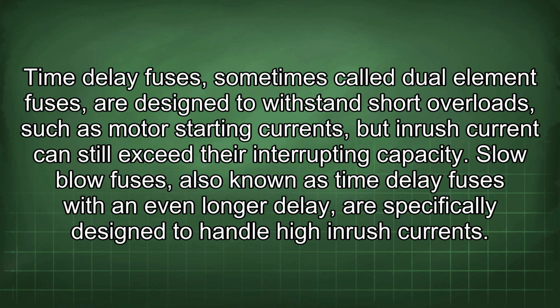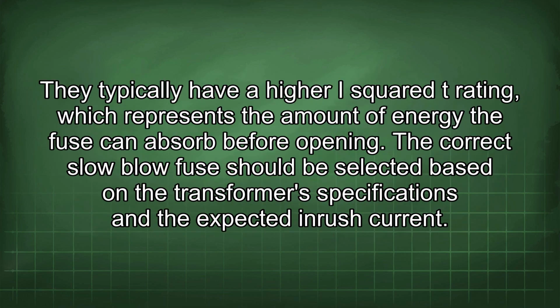Time delay fuses, sometimes called dual-element fuses, are designed to withstand short overloads such as motor starting currents, but inrush current can still exceed their interrupting capacity. Slow-blow fuses, also known as time delay fuses with an even longer delay, are specifically designed to handle high inrush currents. They typically have a higher I²T rating, which represents the amount of energy the fuse can absorb before opening. A correct slow-blow fuse should be selected based on the transformer specifications and the expected inrush current.